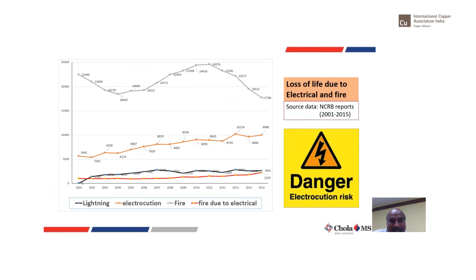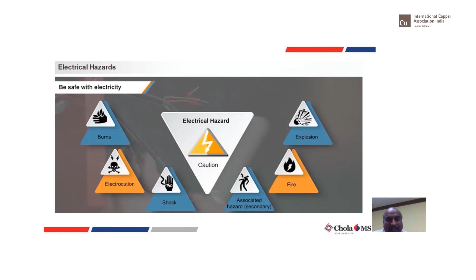Now coming to the hazard, we all know electrical hazard: explosion, fire, shock, electrocution, burns. Invariably, all these are attributed to cables and wires which have malfunctioned. Okay, there could be one area where it could be 50%: if there is an arc flash, it could be a component failure or a terminal lug failure. But of all these electrical hazards, 80% can be attributed to the cable or the wire which is carrying the current, and somebody coming in contact and all that. It's not just the panel equipment. Cable and wires play a major role. That's what I want to reiterate over here.